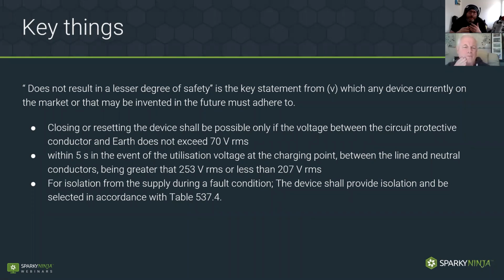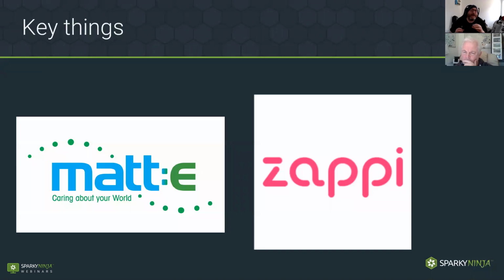Now, some of them, I know, for example, Zappi have their own little residual current detecting monitoring system, but it's not an RCD. They've got their own little current monitor, and they've got electronic equipment that does that. But this does require a bit of trust on the manufacturer's basis. So make sure the manufacturers give you as much transparency as you feel you need from them. I've mentioned Matt-E and Zappi because Matt-E actually don't make charging points. They make devices that go with charging points to achieve protection. And Zappi obviously do make charging points that have this protection in there. These two, from my research, have great transparency about the issues with the regulations and how they are seeking to comply with the regulations. Okay, so you've got to stay with this because, again, this is new technology, new innovations.